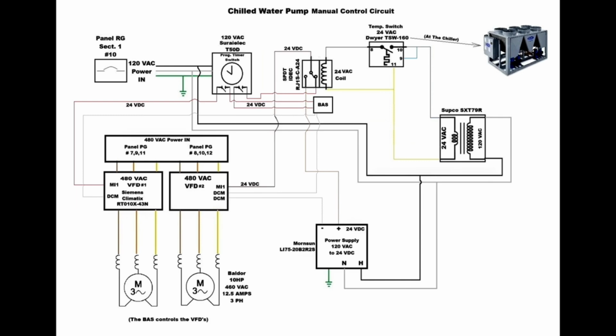The other thing we have here, and again, the reason why we have that power supply is in the event that we want to turn on the VFDs to run the water pumps, we need to be able to send a separate 24 volt signal to those same input terminals on the VFDs. And we're only going to do this on VFD number 2. And it's important that we're not sending two separate 24 volt signals to the VFD terminals at the same time. So that's where this relay is key.